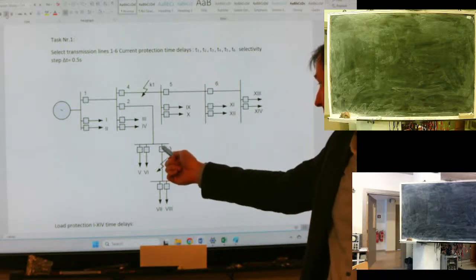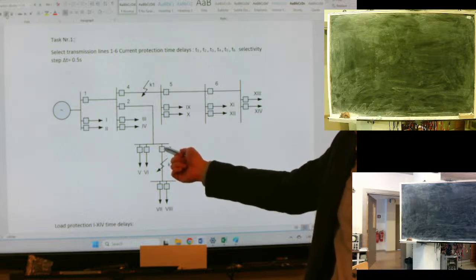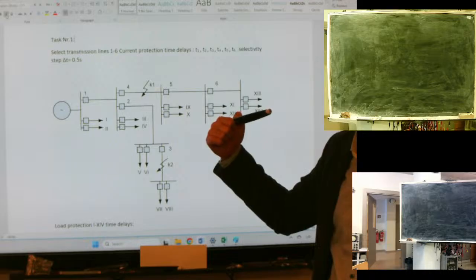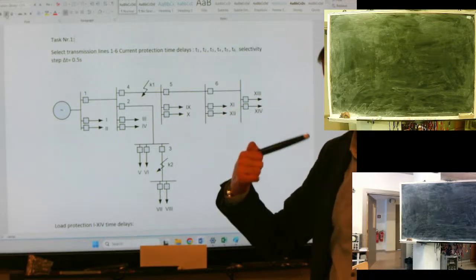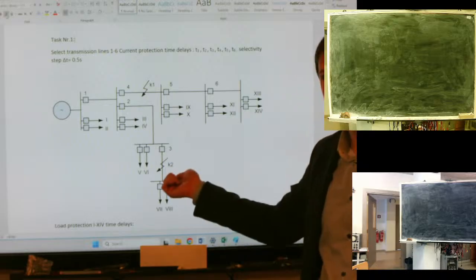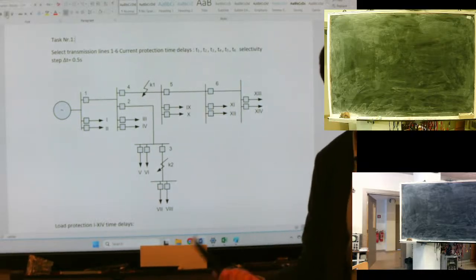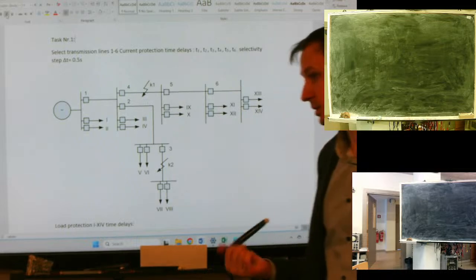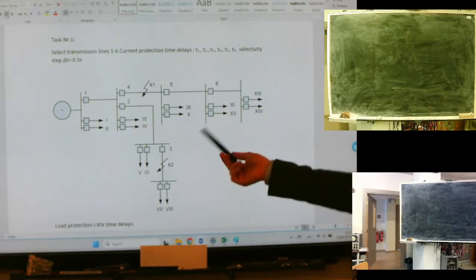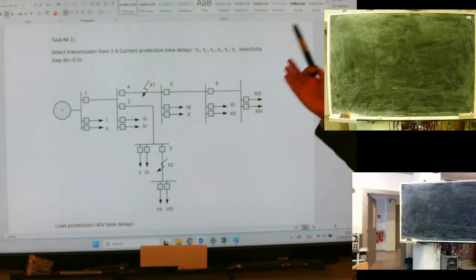You say no. But in case we have any problems with circuit breaker number 3 or with overcurrent protection number 3, to be clear, should number 3 really detect it? Primary, yes. But we want to have a possibility to disconnect the fault element from the grid with other devices. Backup operation. In other words, backup operation. Because you see, a fault is very dangerous for the network. Many reasons can appear with our protection or circuit breaker, but we need to be sure that the fault element will be disconnected in any case.